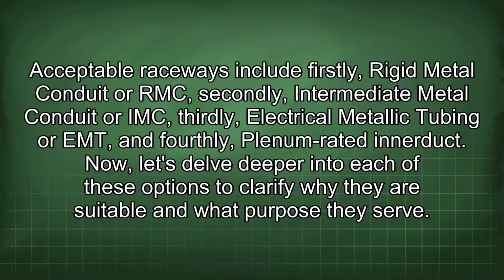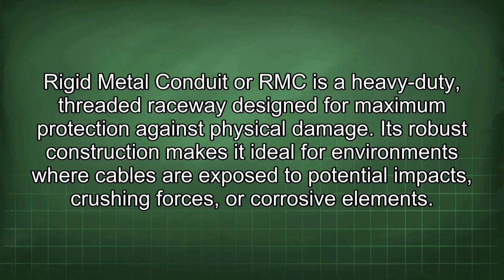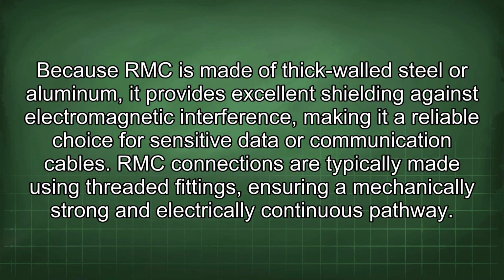Now let's delve deeper into each of these options to clarify why they are suitable and what purpose they serve. Rigid metal conduit or RMC is a heavy-duty, threaded raceway designed for maximum protection against physical damage. Its robust construction makes it ideal for environments where cables are exposed to potential impacts, crushing forces, or corrosive elements. Because RMC is made of thick-walled steel or aluminum, it provides excellent shielding against electromagnetic interference, making it a reliable choice for sensitive data or communication cables. RMC connections are typically made using threaded fittings, ensuring a mechanically strong and electrically continuous pathway.